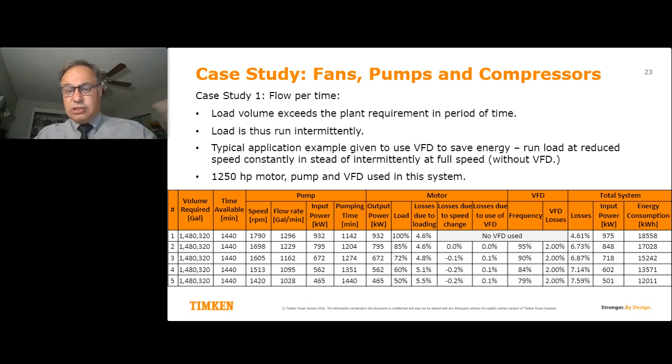The motor runs. I switch it on. I switch it off. So now I use my pumping time, and I multiply it by my input power, and I can get my energy consumption in kilowatt hours. So to do this work in a day will cost me 18,558 kilowatt hours. Fine. That's what I do every day.